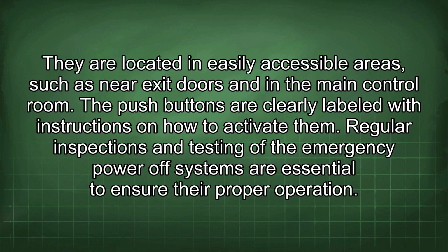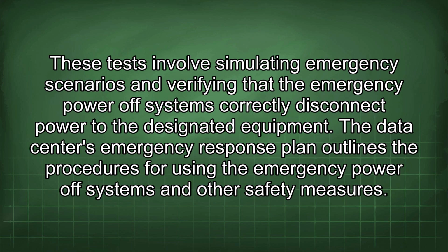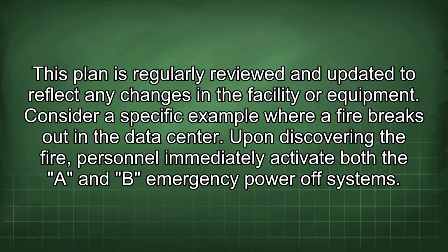Regular inspections and testing of the emergency power-off systems are essential to ensure their proper operation. These tests involve simulating emergency scenarios and verifying that the emergency power-off systems correctly disconnect power to the designated equipment. The data center's emergency response plan outlines the procedures for using the emergency power-off systems and other safety measures. This plan is regularly reviewed and updated to reflect any changes in the facility or equipment.